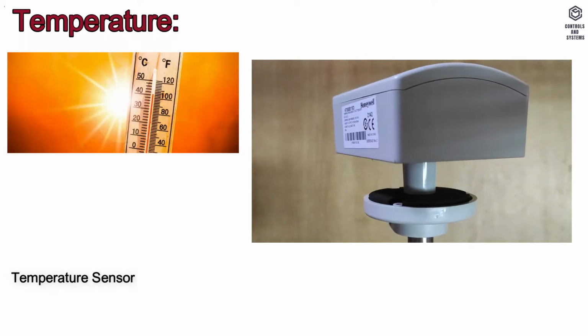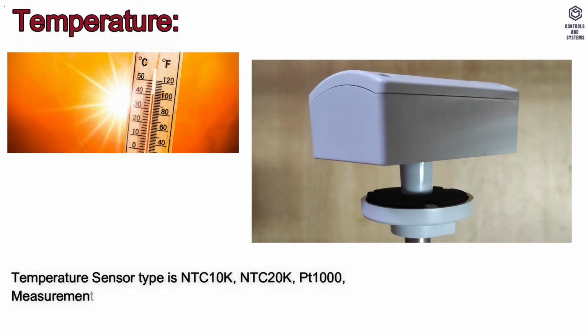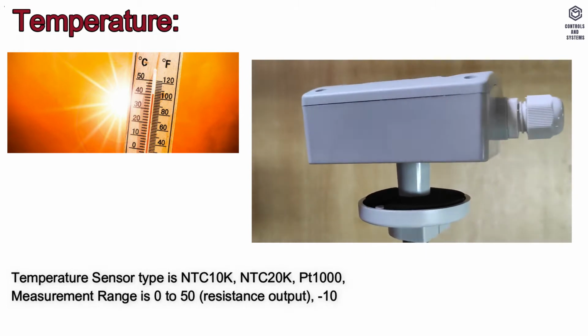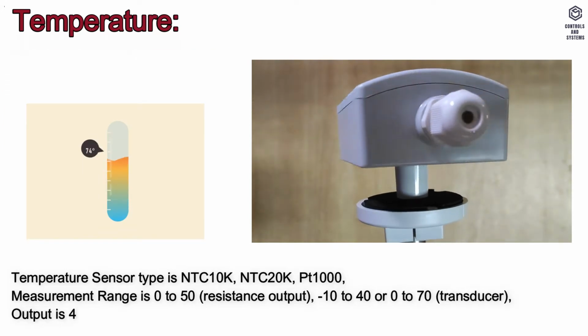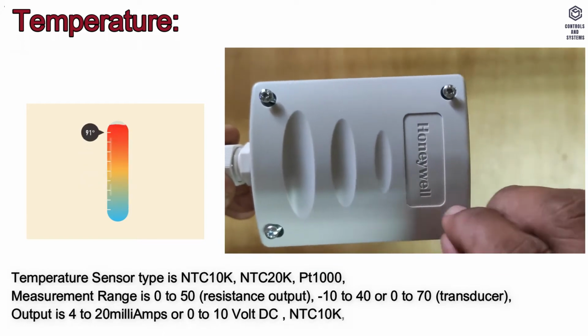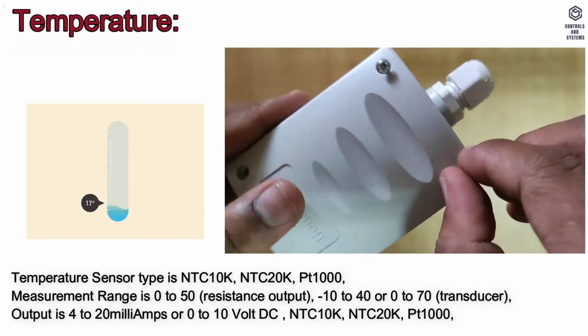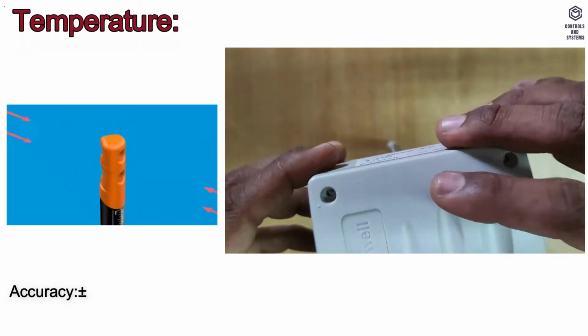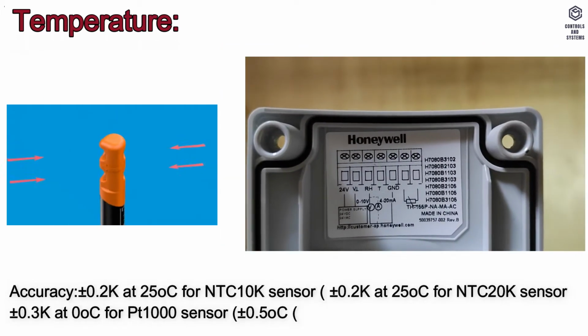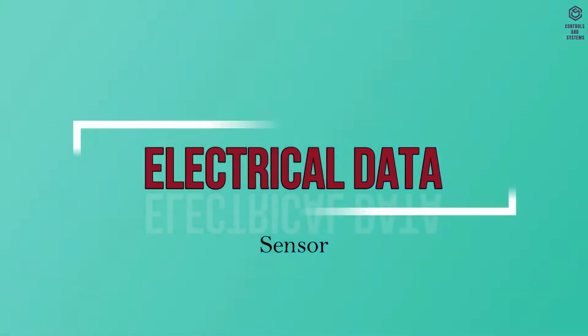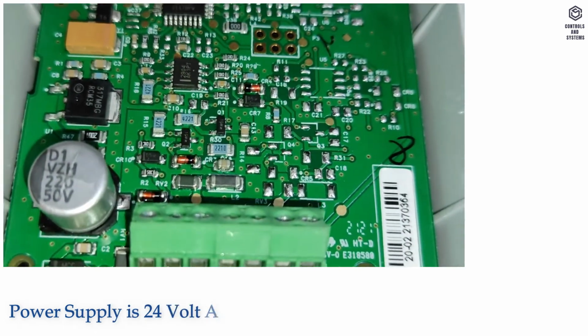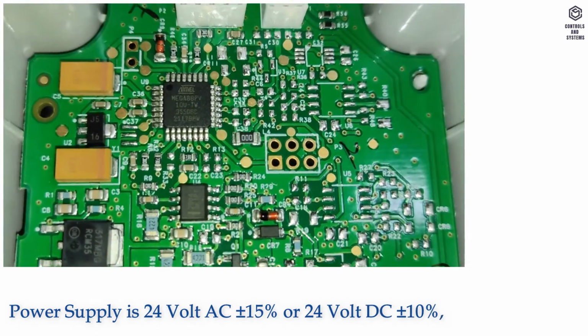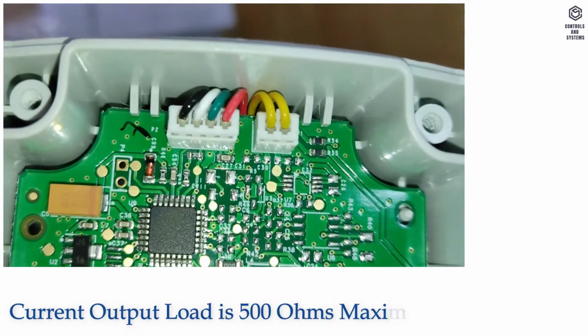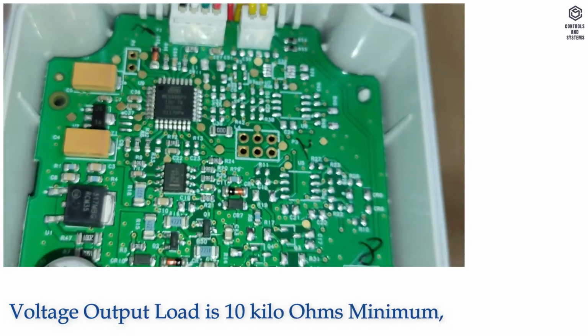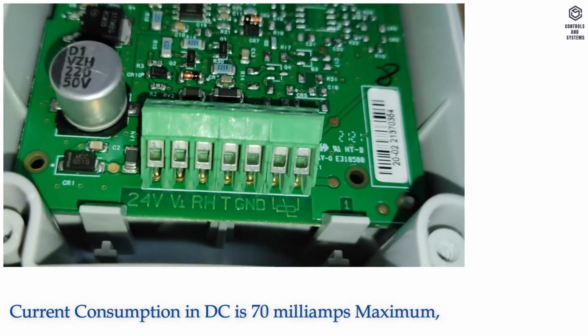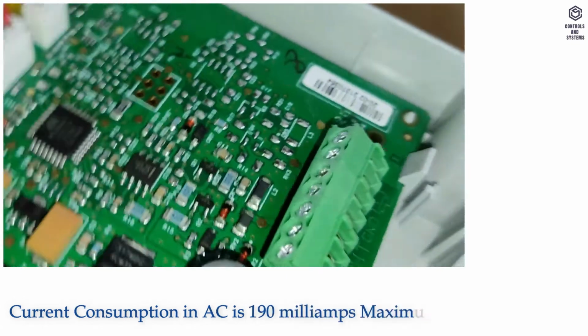Temperature sensor type is NTC10K, NTC20K, PT1000. Measurement range is 0 to 50, resistance output, minus 10 to 40 or 0 to 70, transducer. Output is 4 to 20 milliamps or 0 to 10 volt DC. NTC10K, NTC20K, PT1000 accuracy is plus minus 0.2K at 25°C for the NTC10K sensor. Electrical data: power supply is 24 volt AC plus minus 15% or 24 volt DC plus minus 10%. Current output load is 500 ohms maximum. Voltage output load is 10 kilo ohms minimum. Current consumption in DC is 70 milliamps maximum. Current consumption in AC is 190 milliamps maximum.